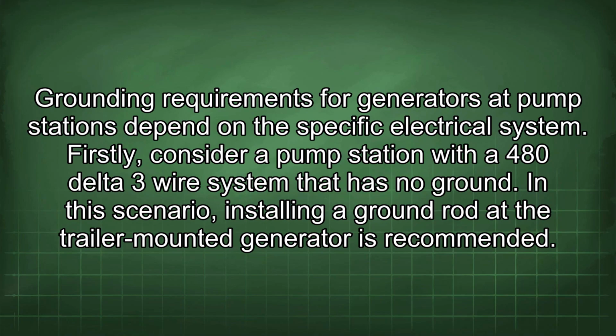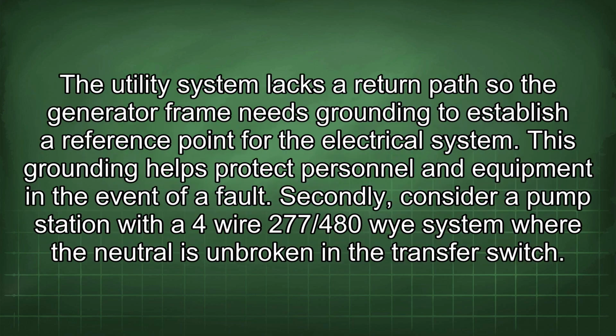Grounding requirements for generators at pump stations depend on the specific electrical system. Firstly, consider a pump station with a 480 delta 3-wire system that has no ground. In this scenario, installing a ground rod at the trailer-mounted generator is recommended. The utility system lacks a return path, so the generator frame needs grounding to establish a reference point for the electrical system. This grounding helps protect personnel and equipment in the event of a fault.